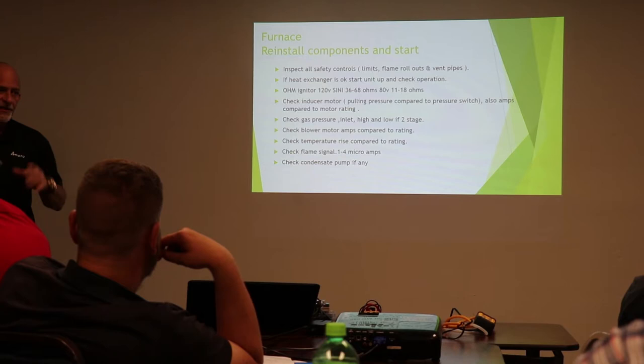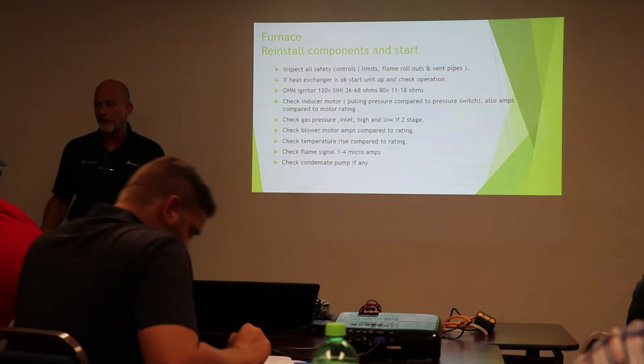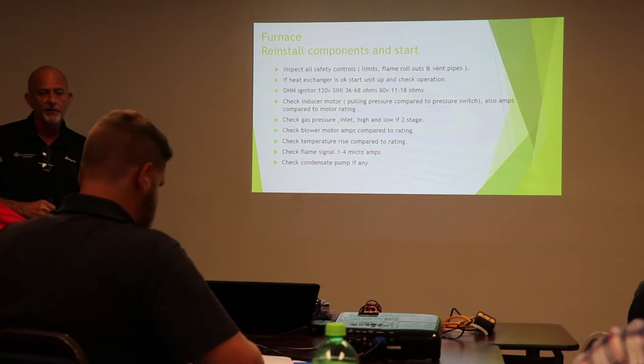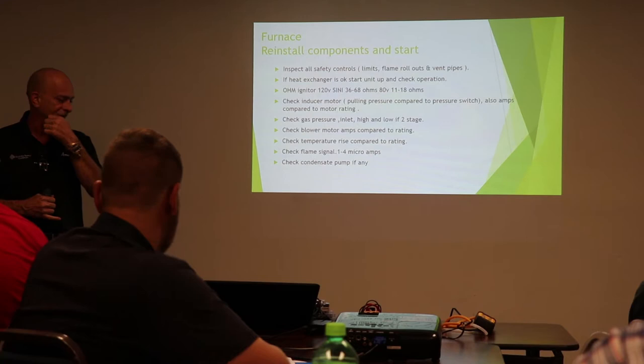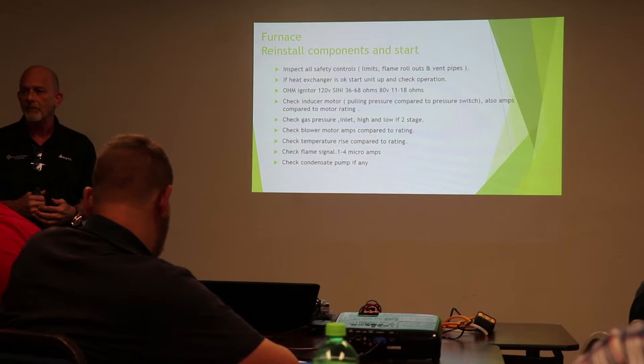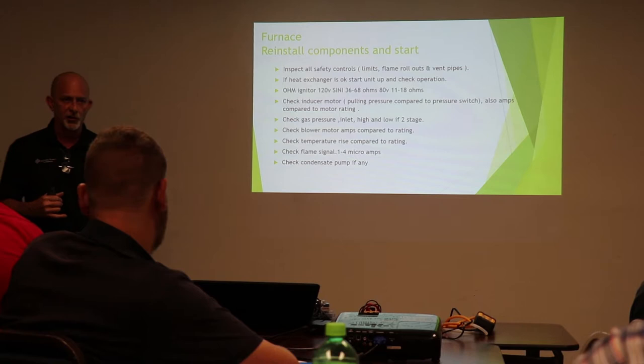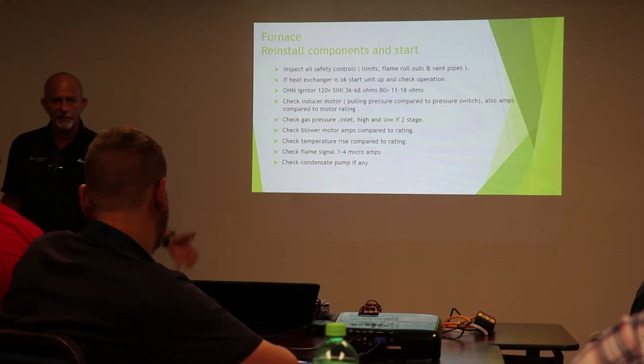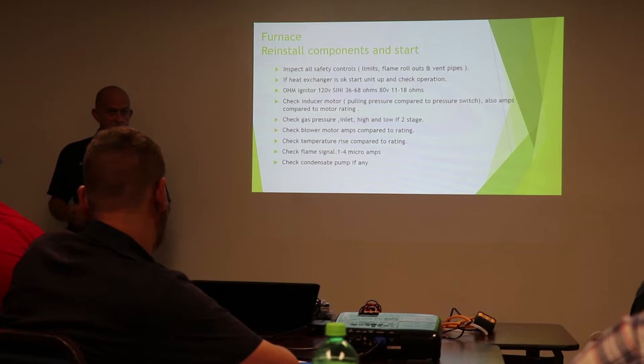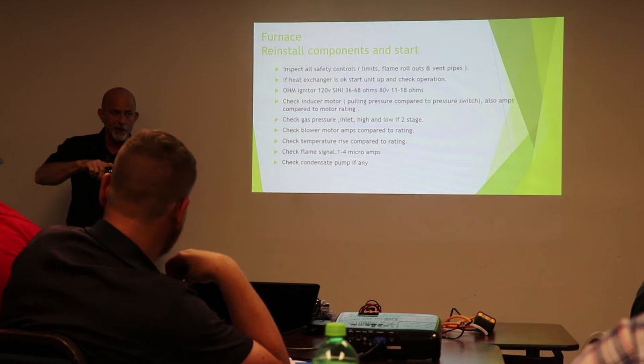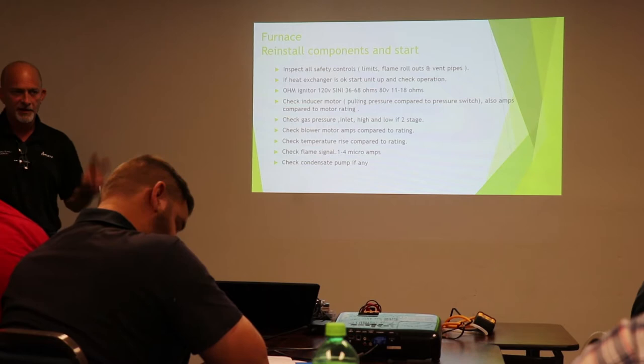Also, when we're checking that, make sure we have a good ground on everything. Make sure our burner grounds are attached. Make sure our main ground, if it's there when the furnace was wired up, is attached. I've had furnaces work fine for years. Then one day they won't sense flame. No ground wire. But for years it actually used the conduit to ground itself. But it is not a true ground. And out here you guys use Romex and BX, flexible. That's got a separate ground in there. Usually I see guys do this, they got their white and black, they take that silver one, throw it out of the way, it's in the way, they never hook it up. Don't rely on BX, even conduit, to be a good ground.